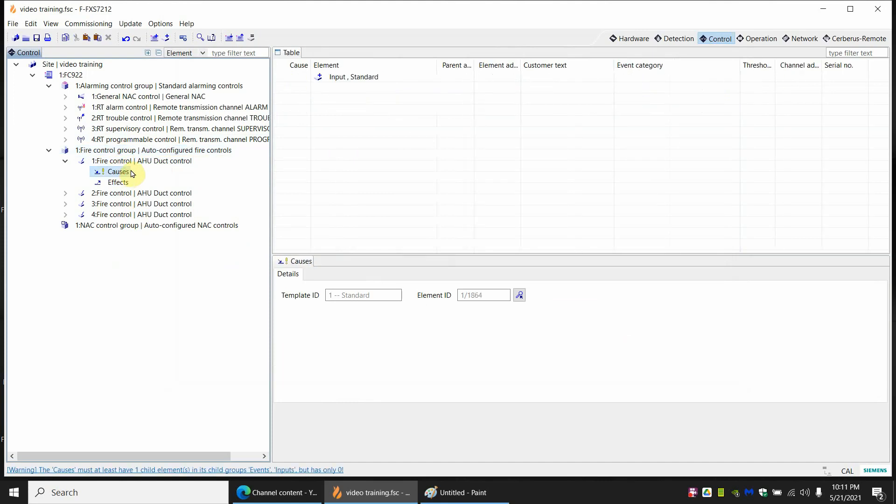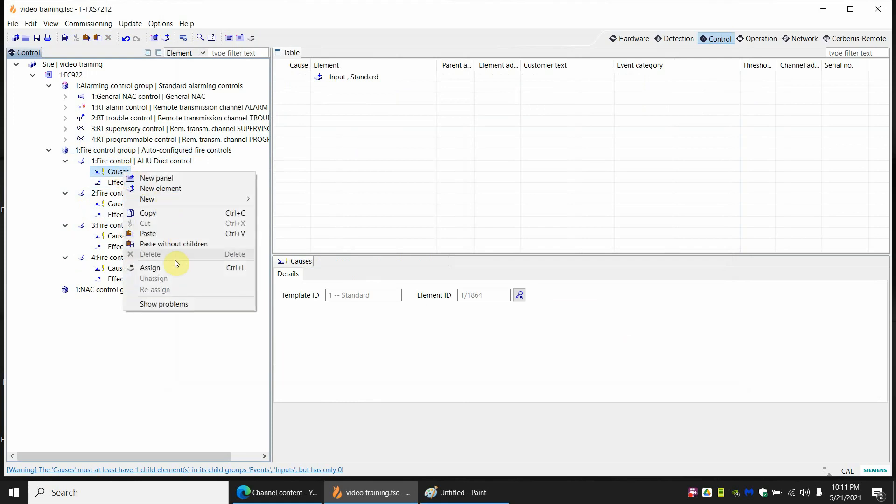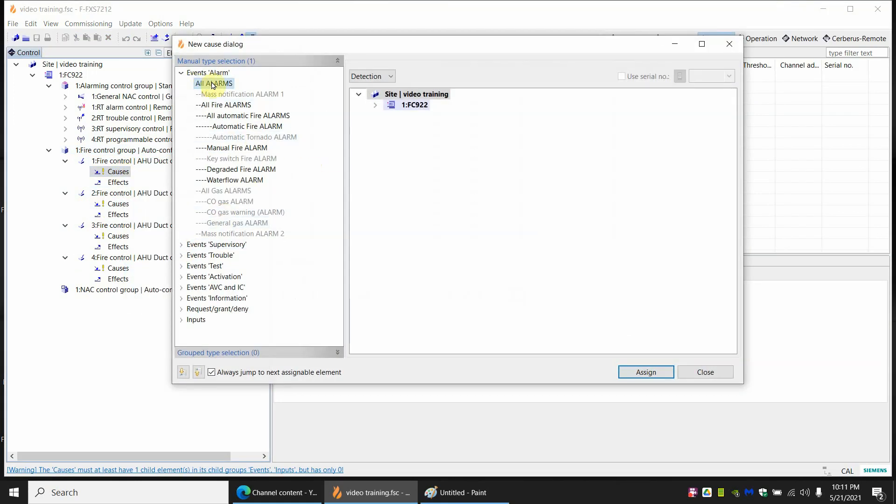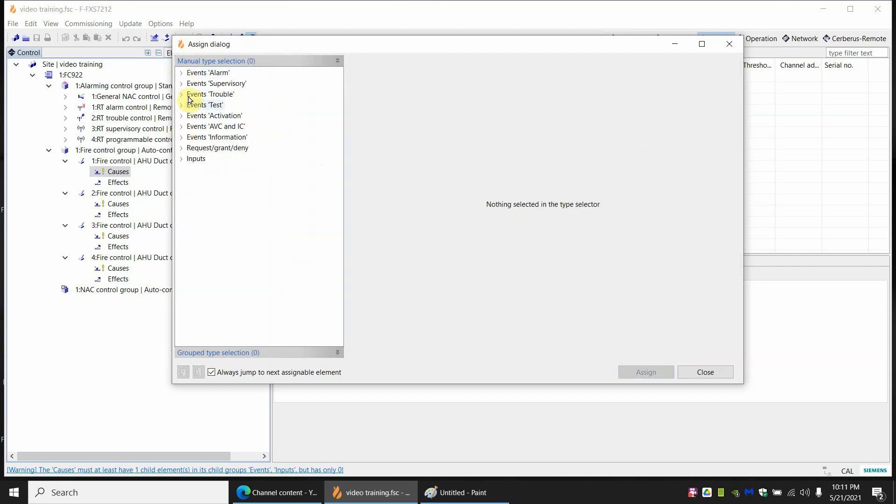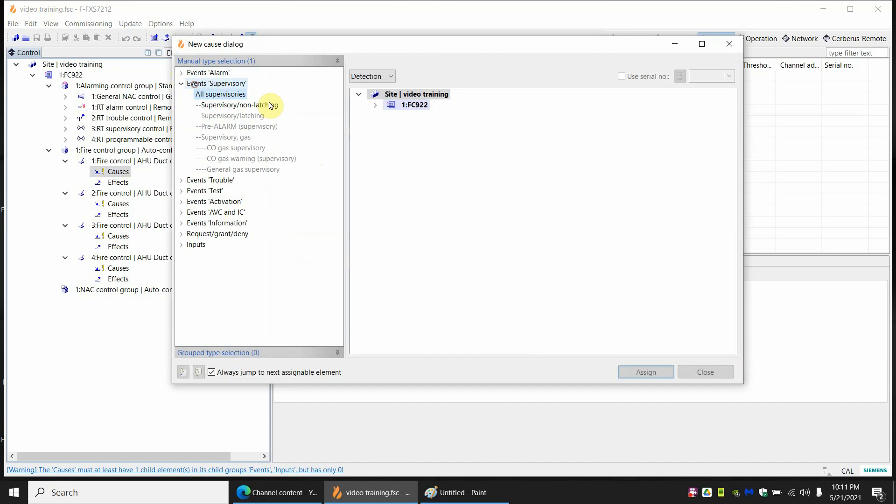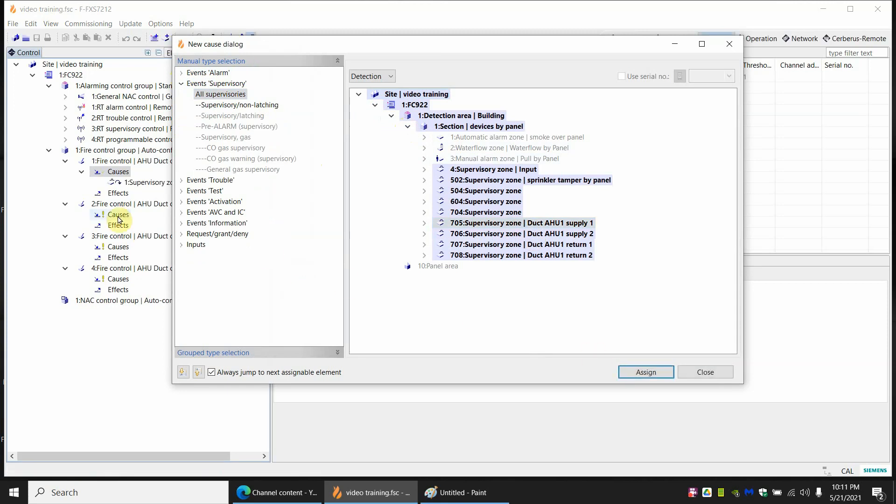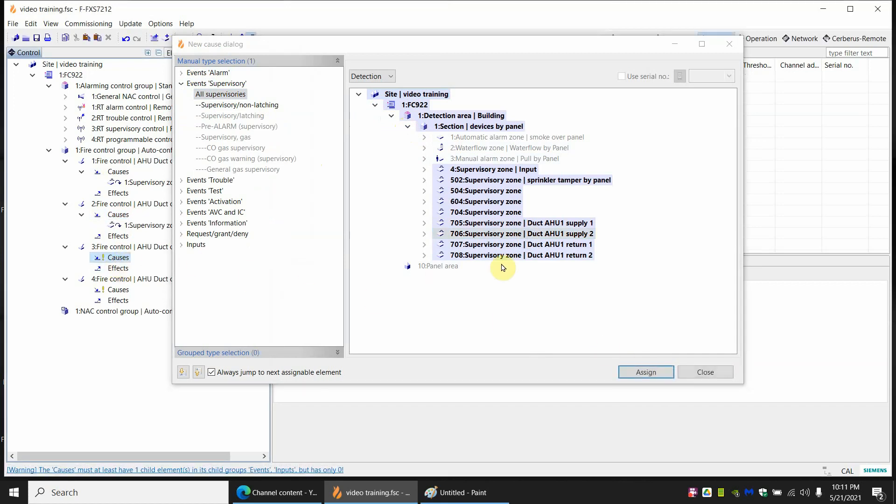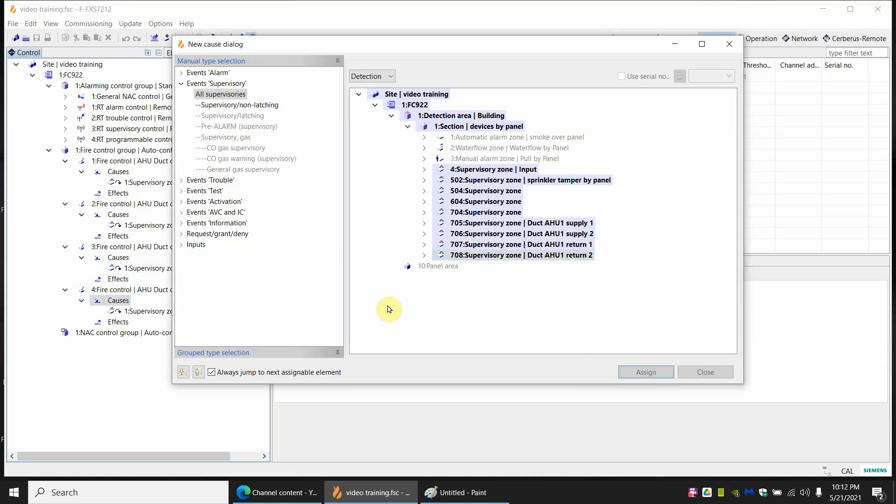Alright so now we're going to go ahead and start assigning. I'm going to open up all these because I'm going to assign everything at once. So assign this cause. The cause is not an alarm because we did supervisory. So you'll never find it here. But you can frustrate some people. You're like I see it right here. Why can't I click it? Because it's supervisory. And you're only looking at alarms. So let's open up supervisories. Now you should be able to open up and find it. There we go. Duct one supply. Assign. We'll go ahead and continue here just for all the causes. Duct two supply. Return one. And return two.